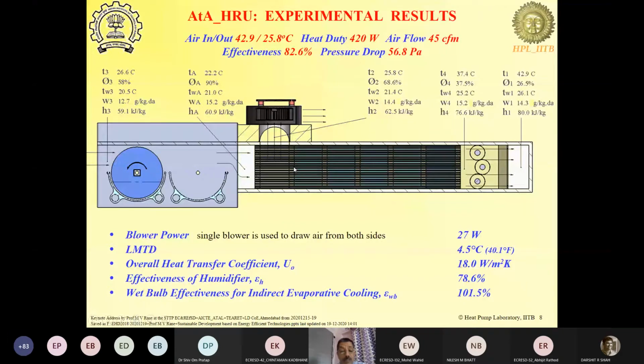Okay. And of course, if you go through the details, you'll see that the blower power was very small. And it can be further reduced, of course. The pressure drops are much lower than the conventional heat exchangers of this type. Typical conventional heat exchangers, the pressure drops are of the order of 150 to 200, 250 Pascal. In our case, it was less than 50 Pascal. Okay. Less than 60 Pascal.